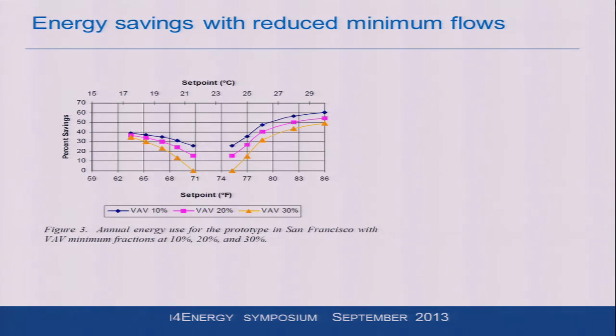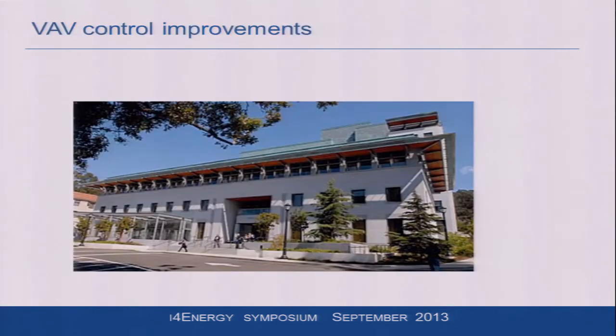If there's no load in the space, you don't need a flow. But if you're capped at 30%, you're going to be pumping air in at whatever the supply air temperature is. You may have to reheat it. And odds are you'll certainly use energy. You can see your savings in this case are, again, in the 30 to 40% range. But you'll also very likely overcool people. And this is something you can see here.